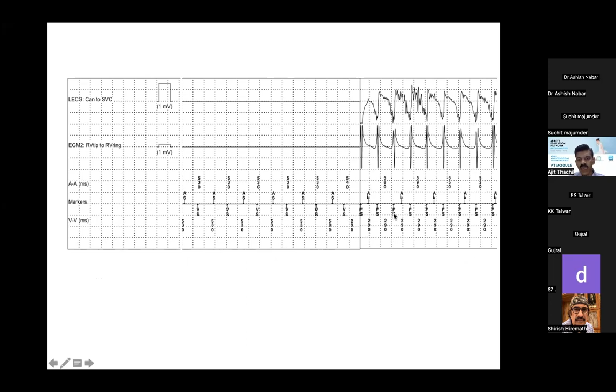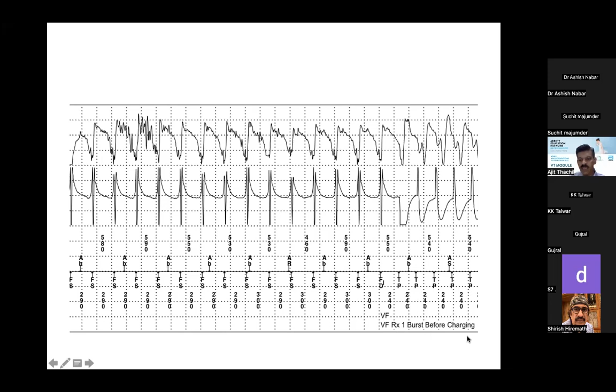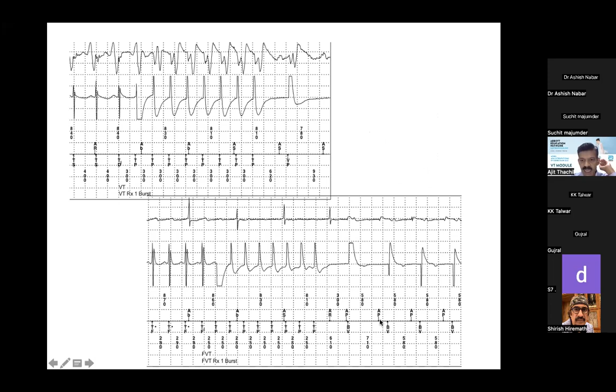Here's another one. ASVS, ASVS, ASVS, meaning likely sinus rhythm, ASVS, and then an FS, a beat sensed in the ventricular fibrillation zone. FS, FS, FS, FS. Enough beats are sensed in the ventricular fibrillation zone. Once you sense enough beats, it changes the annotation to FD, ventricular fibrillation detected, and then TP, TP, TP. So that is a ventricular fibrillation burst before charging. You can burst the anti-tachycardia pacing before charging or during charging. So TP, TP, and then ASVP. So it is sinus rhythm in the atrium and ventricular pacing in the ventricle. In this case, this is APBV, that is atrial pacing and biventricular pacing. So those are all the different annotations you will find.